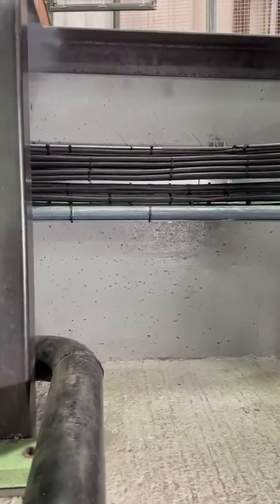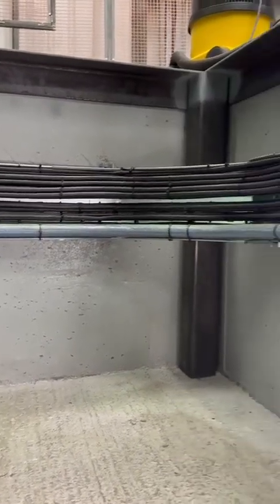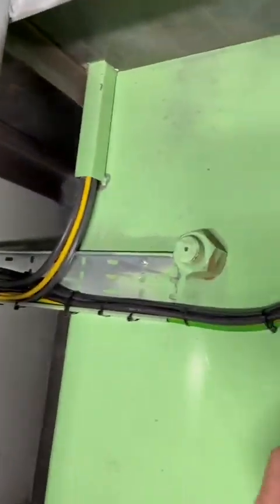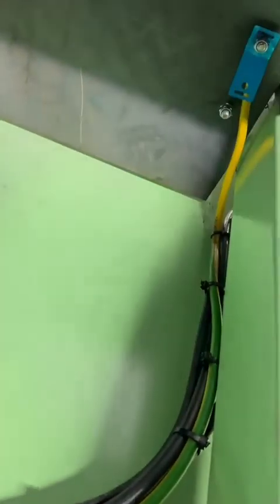Machine now, we've put new cables in, they're all neatly clipped around this tray work here, which come to the control panel. We're underneath the control panel. The control panel's been bolted down to the floor. We've all got proper armour glands in, and they're fixed in the panel. As we come around the tray work and up here, we've put an earth bond on the checker plate floor in there.